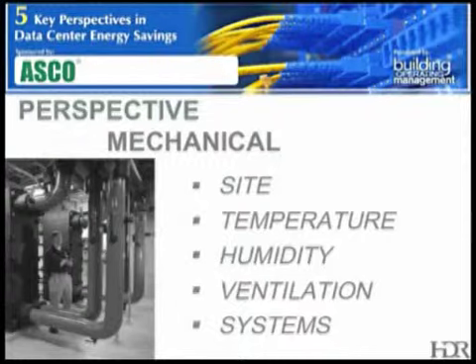And I think for a majority of the work that we do, we always target to design within the recommended range, which is roughly 65 to 80 degrees entering the equipment, with some minimum dew points of 42, relative humidity max of 60%, and a maximum dew point. So it sets that boundary that we were showing on the psych chart.